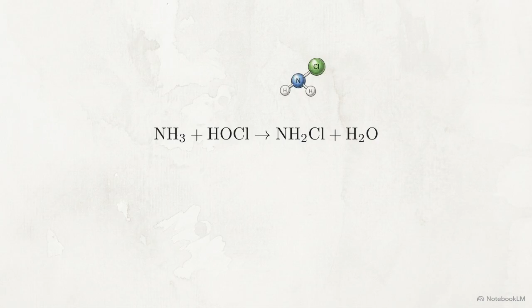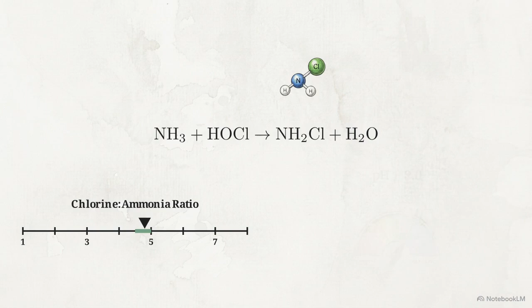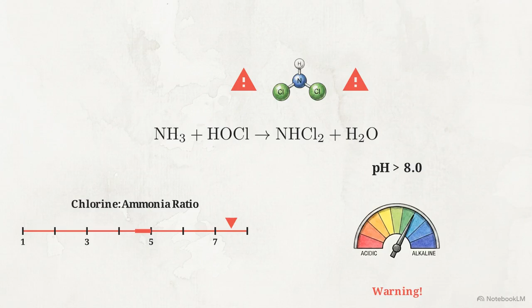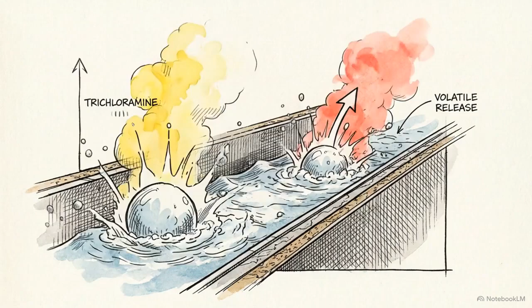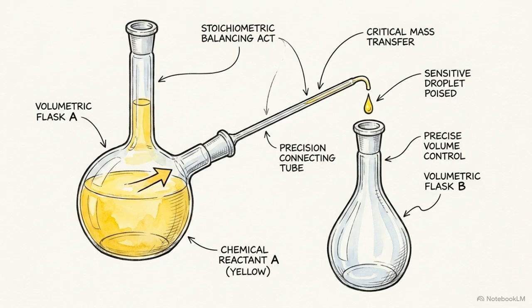This equation shows the stoichiometry required to produce the molecule utilities want, monochloramine. This requires specific constraints: a chlorine to ammonia weight ratio between 4.5 and 5 to 1, at a pH above 8.0. Exceeding a 5 to 1 ratio thermodynamically destabilizes the solution, forming dichloramine. Once dichloramine forms in the distribution system, it degrades rapidly and generates severe taste and odor complaints from consumers. Pushing the ratio even higher triggers the formation of trichloramine, a highly volatile compound that easily gasses out of the water entirely. Generating an effective secondary disinfectant is a highly sensitive stoichiometric balancing act.